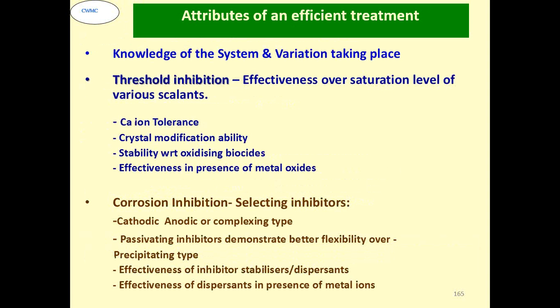Threshold inhibition is the lowest level of chemical that can be used for treating a particular system. So it should have good calcium crystal modification ability, stability with respect to oxidizing biocide, and effectiveness in the presence of metal oxide. Corrosion inhibition you can do by selective inhibitors, cathodic, anodic or complexing type. Passivating types demonstrate better flexibility over precipitating types. Effective inhibitor stabilizer dispersants. Effective dispersants in the presence of metal ions.